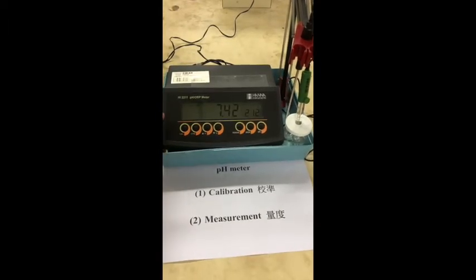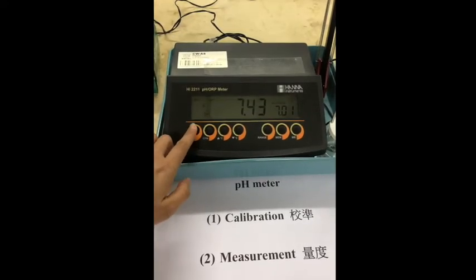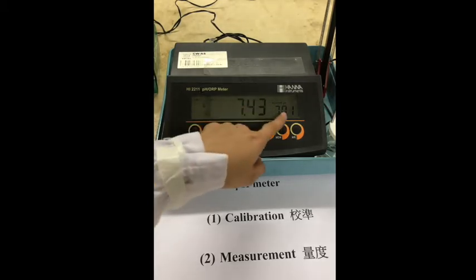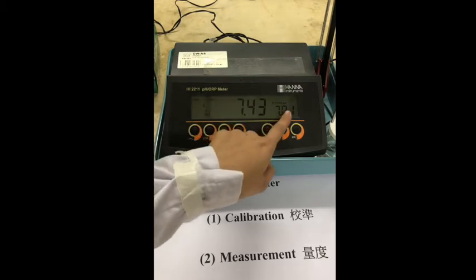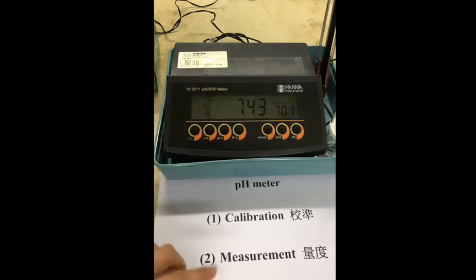For the calibration procedure, we need to change the mode to calibration mode by pressing the button CAL. The display will change once the button is pressed. You will notice the CAL icon, pH, and BUF, which means buffer. And the pH of the buffer required, which is 7.01.